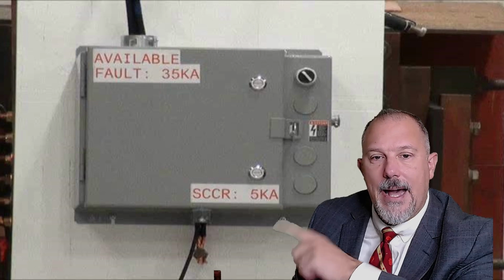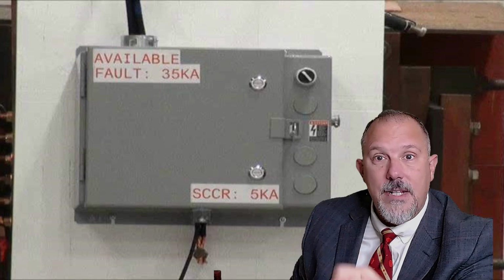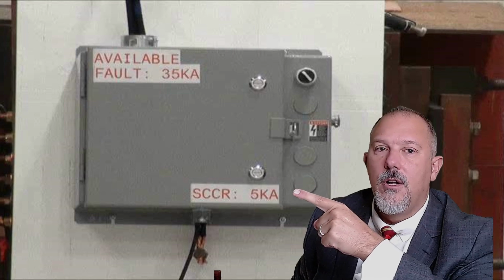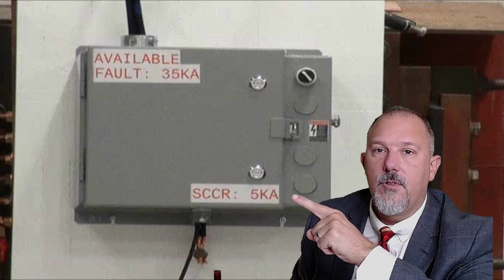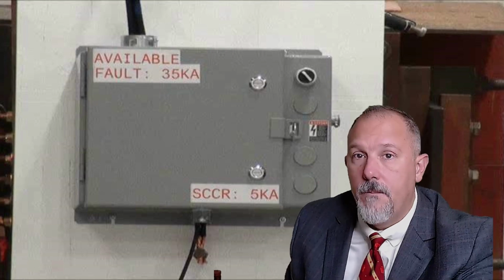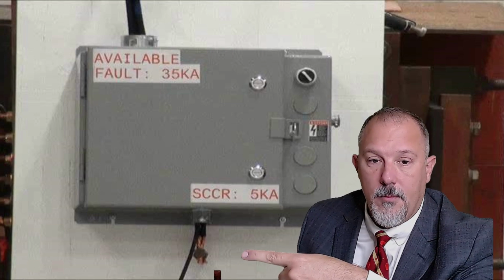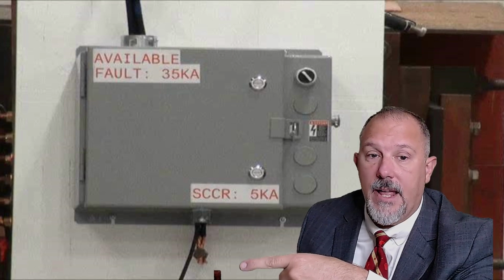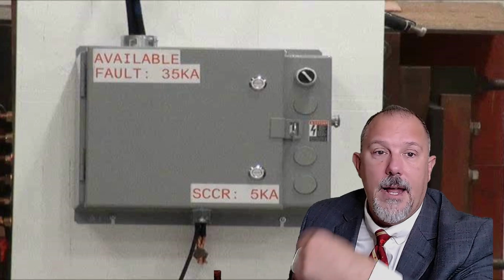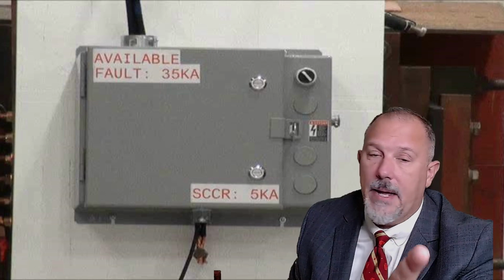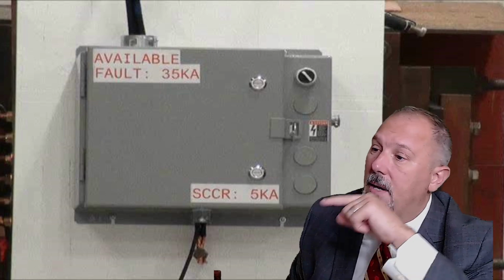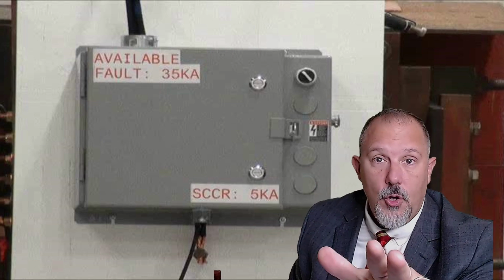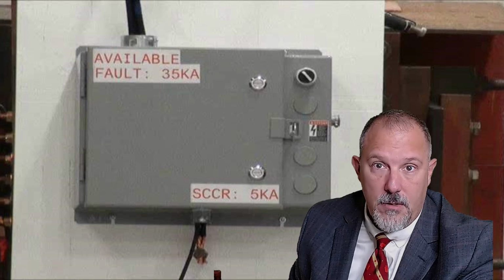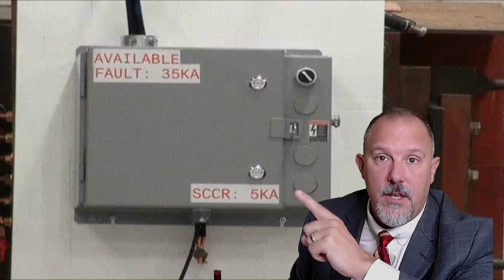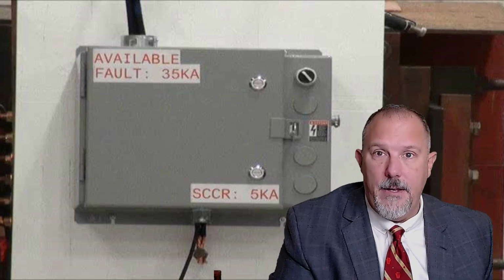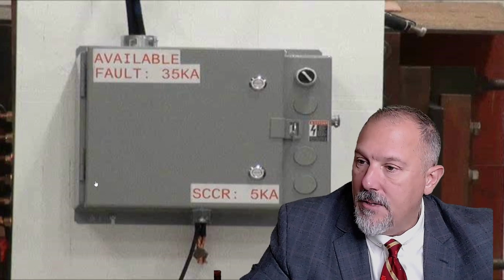That's the conductors coming out of this equipment, and it's shorted together. So inside this box are components that must carry and deliver the fault current to this short circuit. I tied the hot and neutral together, and I know the fault current passing through this is going to be 35,000 amps, but it's only rated for 5,000 amps. You are going to see damage because I am misapplying this product. I'm violating 110.10 of the National Electrical Code. Let's see what happens.